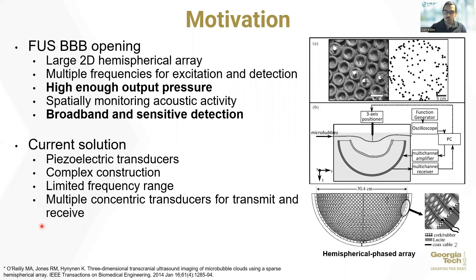The piezoelectric transducers are the most widely used technique in blood-brain barrier opening. This technology has a challenging fabrication process, especially in 2D array forms. Moreover, the fixed frequency range of piezo transducers limits the treatment envelope, and it was previously proposed that multiple concentric transducers can be used simultaneously in blood-brain barrier opening.